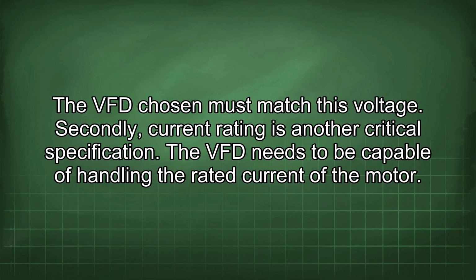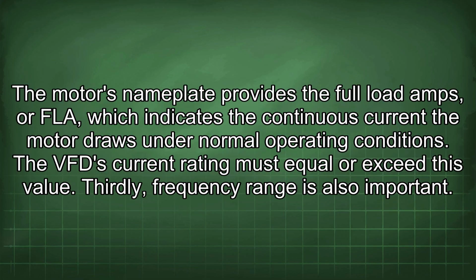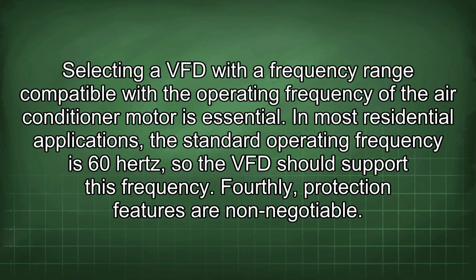Secondly, current rating is another critical specification. The VFD needs to be capable of handling the rated current of the motor. The motor's nameplate provides the full load amps, or FLA, which indicates the continuous current the motor draws under normal operating conditions. The VFD current rating must equal or exceed this value. Thirdly, frequency range is also important. Selecting a VFD with a frequency range compatible with the operating frequency of the air conditioner motor is essential. In most residential applications, the standard operating frequency is 60 Hz, so the VFD should support this frequency.